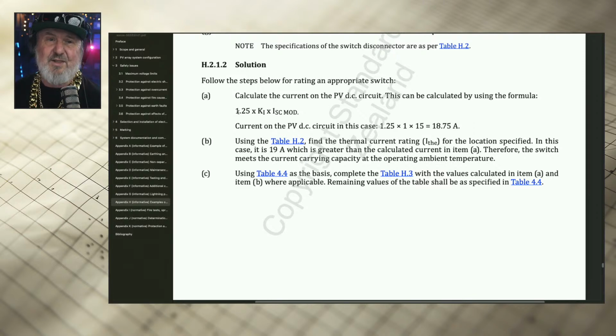It's been around ever since the 2012 edition of 5033, because it referred to the DC circuit, and people seemed to ignore that for quite a while until it was really hammered home in the latest update. So we multiply those through and we find that our 15 amp ISC, with a 25% safety margin, is going to have a short circuit current of 18.75 amps. Okay, so that's what we've got to be able to interrupt safely with an I make, I break setting.